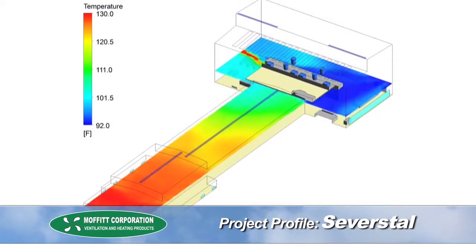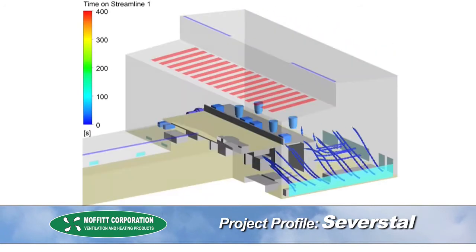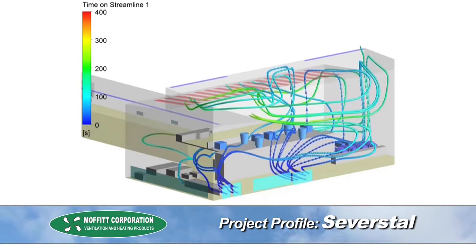We developed a 3D CFD model. This model showed how the temperature changed throughout the different elevations of the building, allowing Moffitt to determine the amount of intake air and the amount of outlet air required to reduce the temperatures to bring it within 10 degrees of outdoor ambient conditions.